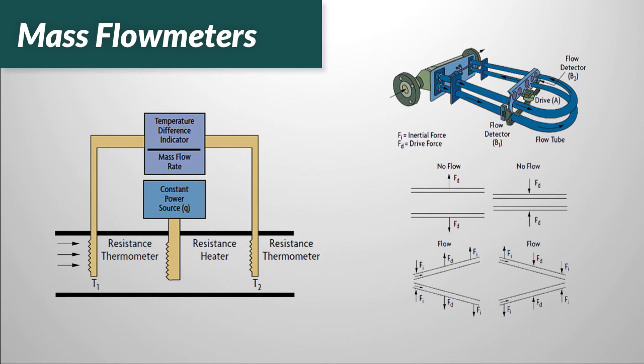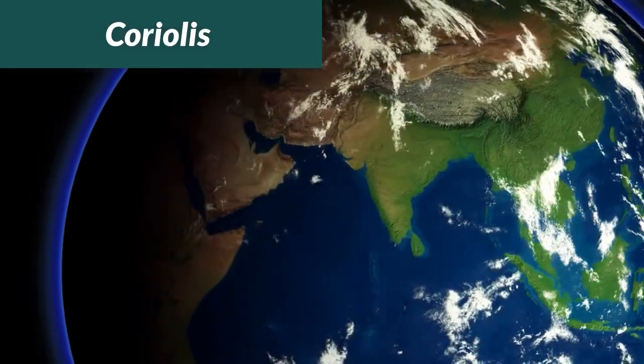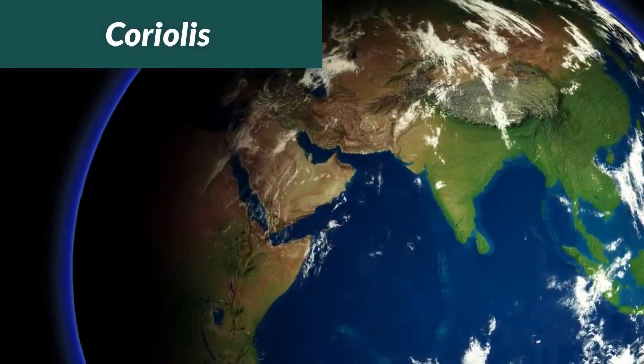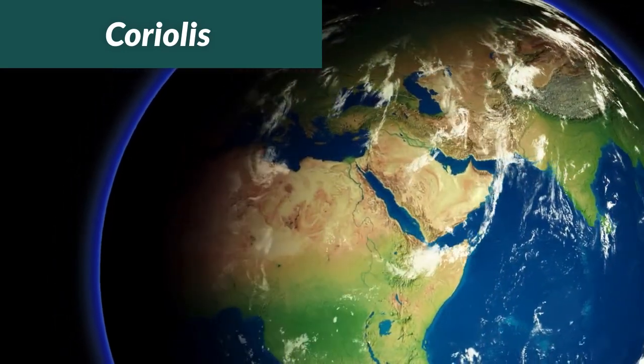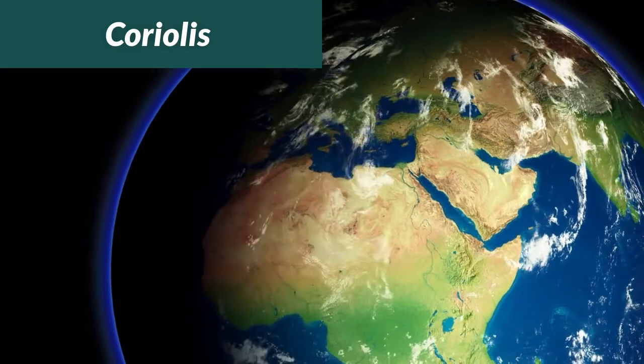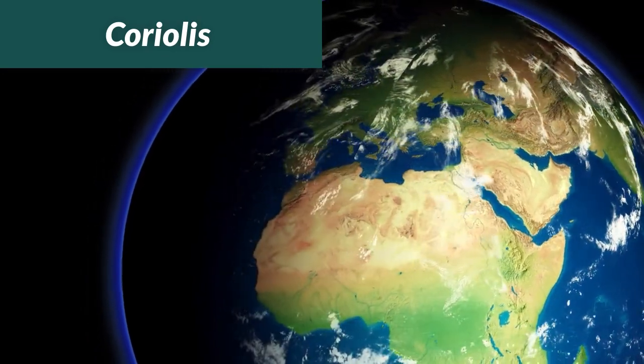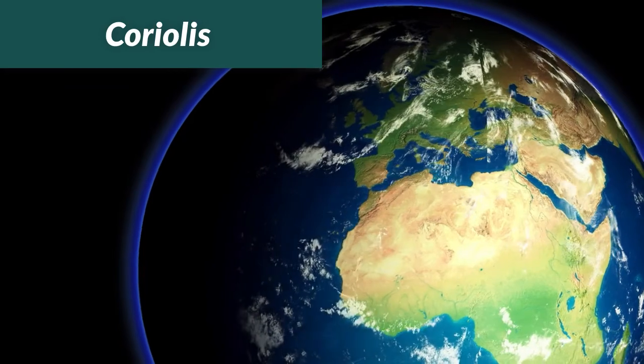The final two technologies that we'll talk about on our tour are mass flow meters, so named primarily because of their relative insensitivity to variations in temperature, pressure, and other process conditions that can significantly affect the mass flow rate calculated from a volumetric device. The Coriolis meter takes advantage of the phenomenon that Gustav Coriolis first observed as the tendency of bodies moving on the surface of the Earth to drift sideways because of the eastward rotation of the planet, to the right of the motion in the northern hemisphere and to the left of the motion in the southern hemisphere.